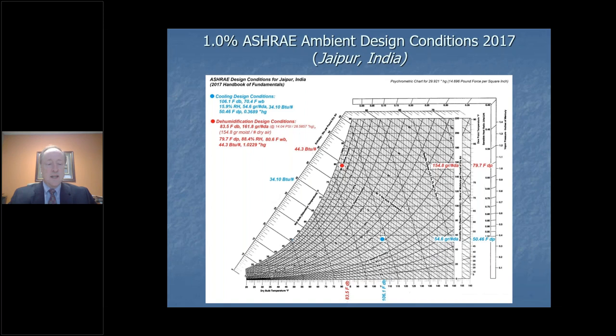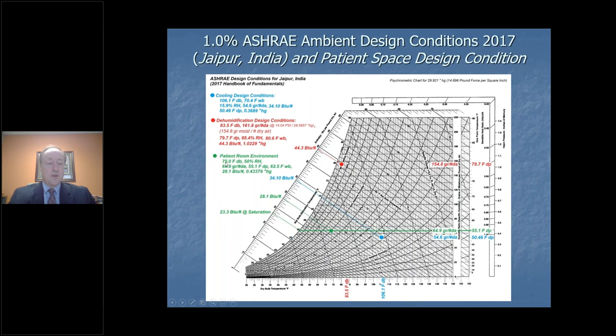Well, let's look at some numbers. Let's say we wanted to design this space to be a patient room or an office building with the doctor's offices or your classroom, and let's say we want a 75 degree dry bulb and 50% relative humidity. Here are all the other points on the psych chart. That's this point right here. So if we design for the cooling day only, from this point to that point, we can calculate through the enthalpy over here how much tonnage, how much cooling we need to get from here to here. And then we can do the same with the peak dehumidification day, going from this point to this point. You'll see there's a big difference in the enthalpy there. So the next chart is going to point that out.